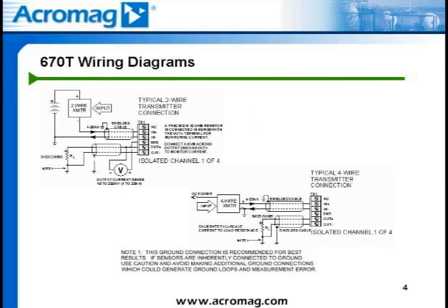Here we show electrical hookups based on DC current applications. First, for a two-wire transmitter field device, it involves the use of a DC power supply to power the field transmitter and the input loop. Going around the loop starting with the positive terminal of the two-wire transmitter, wire to the positive side of the DC power supply. From the negative side of the power supply, wire to the IN-minus terminal of the 670T isolator. The negative connection on the two-wire transmitter simply ties in with the IN-plus terminal. On the output side, power is derived from the input loop, so no additional power supply is required. Connections are simply the out-plus terminal to the positive load connection and the out-minus terminal to the negative load connection.